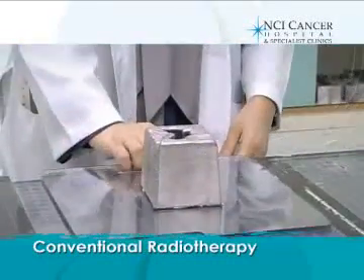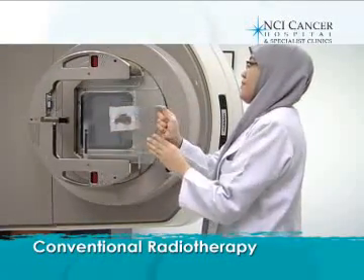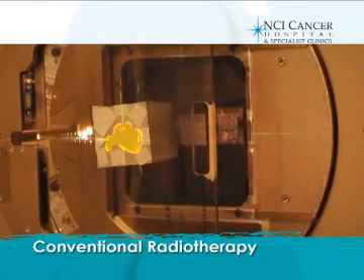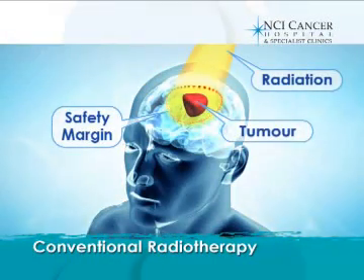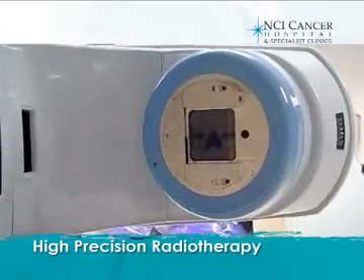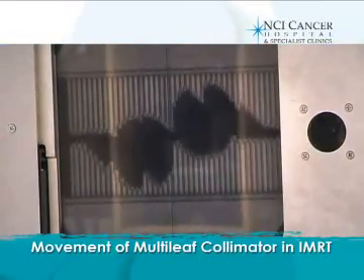This is a typical lead alloy block used to shield organs not receiving radiation. Each block is handmade. Patients receive radiation on the tumor area using this method, and a large safety margin is allocated to the tumor treatment area. In today's technology, the multi-leaf collimator is designed to increase efficacy in the delivery of radiation doses to patients.